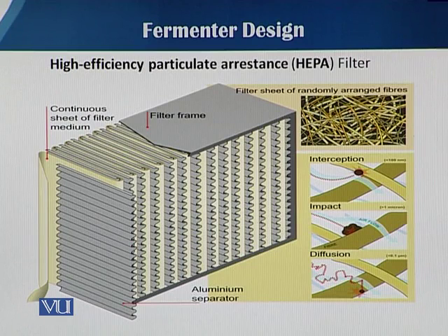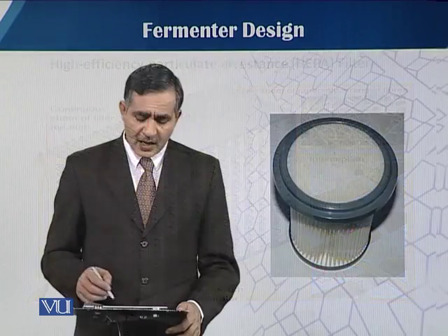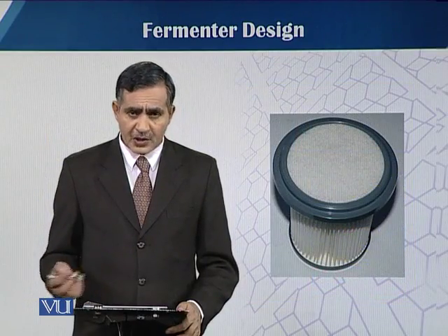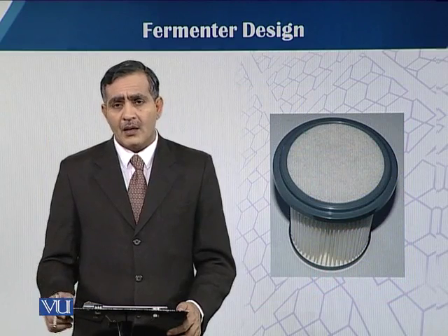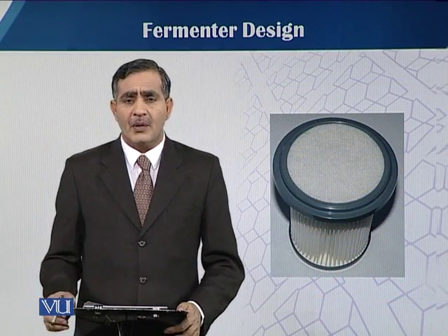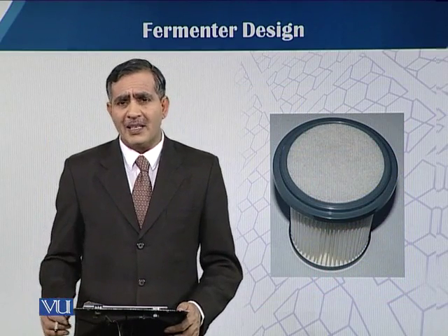You can see in this slide the arrangement and the packing of that material, with a pore size of 0.2 micron to 0.45 micron. But this is the small size of HEPA filter that is mostly used in different fermentation and other biomedical equipment.